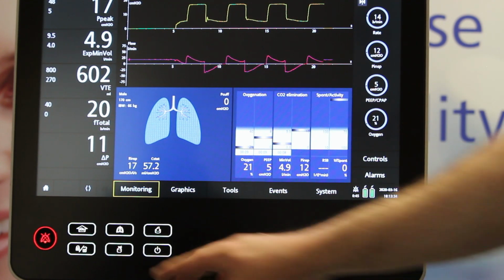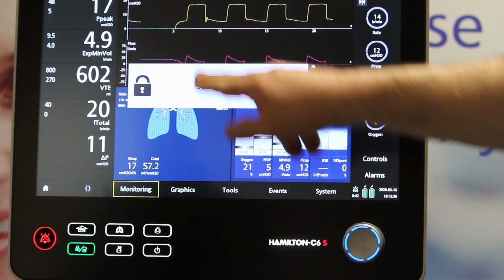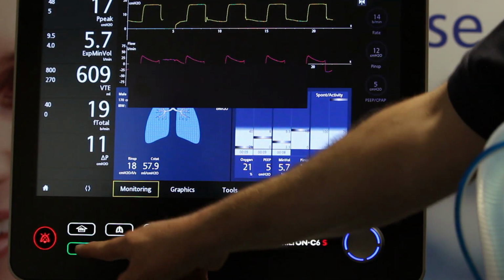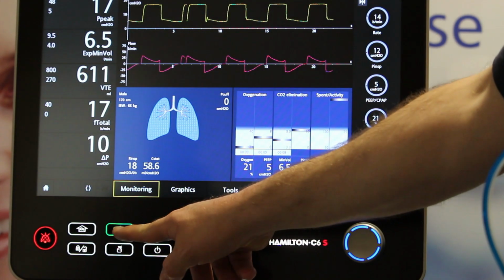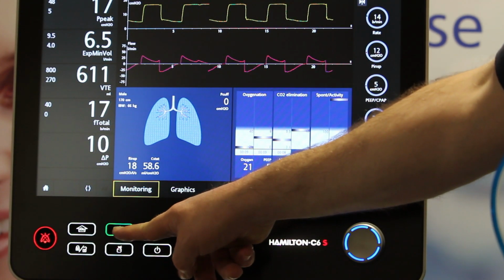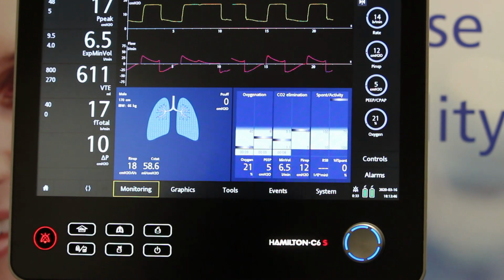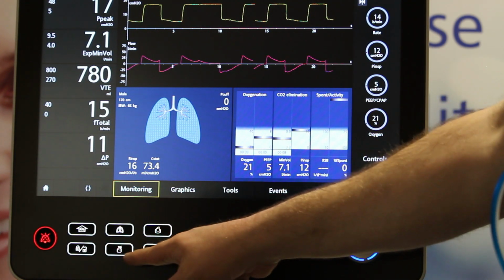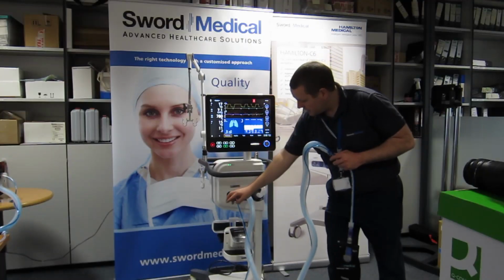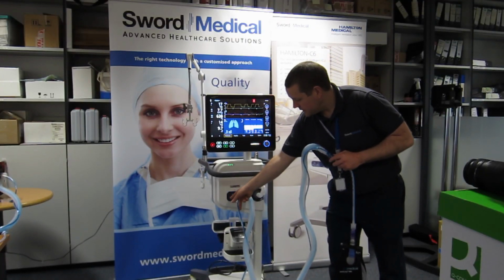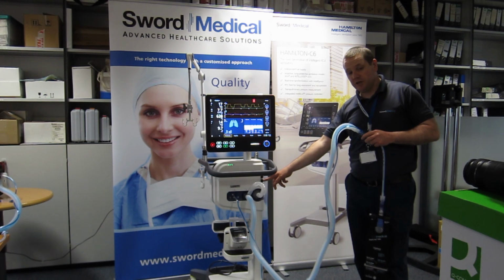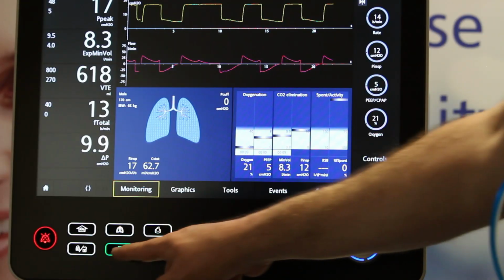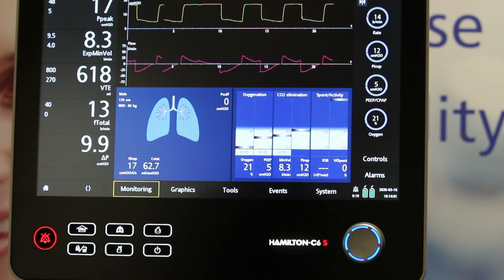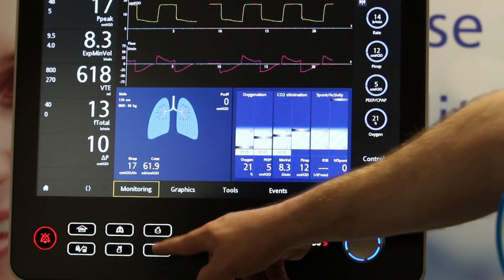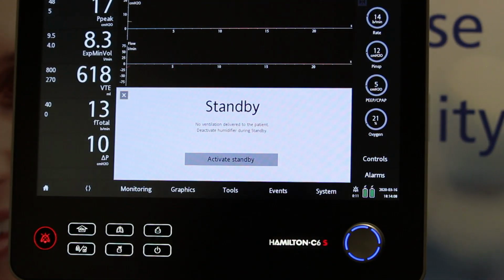There's a screen lock here. When I press it, it locks the screen so I can't do anything on the screen. I have a mandatory breath, which allows me to deliver a breath to peak and holds it there for as long as I hold the button. I also have the nebulizer button here, so this nebulizer button will turn on this pneumatic nebulizer here, which is different to my Aerogen nebulizer, which plugs in here and is controlled through the handset. And then I also have my data transfer button, and I have my power button, and the only way to stop the ventilator ventilating is you press the power button, and if you activate standby, it'll bring you back into the standby screen.